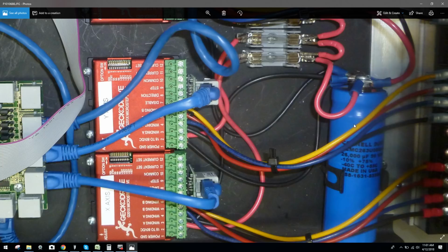But when I see this, you can see the quick connects are insulated and you have no shielding at all on these motor outputs. What you're basically doing is inviting in the potential for EMI. Now, let's look at the facts here. If these are not shielded, most likely the Ethernet cables are not shielded. Nothing in this chassis is shielded.